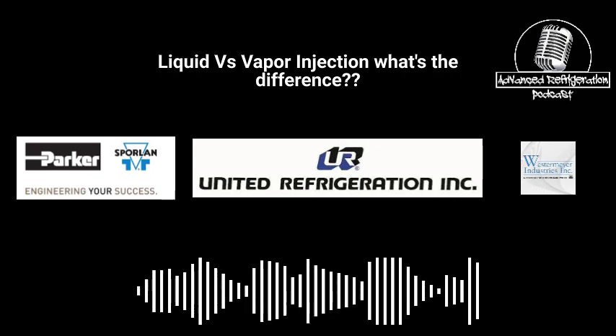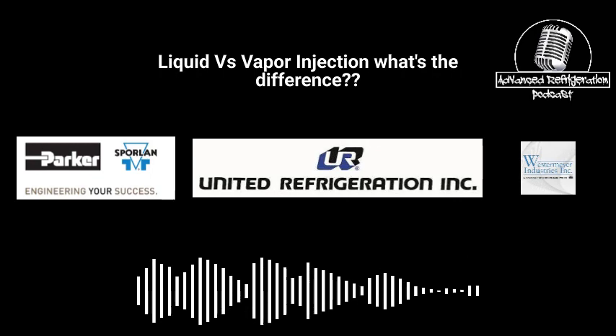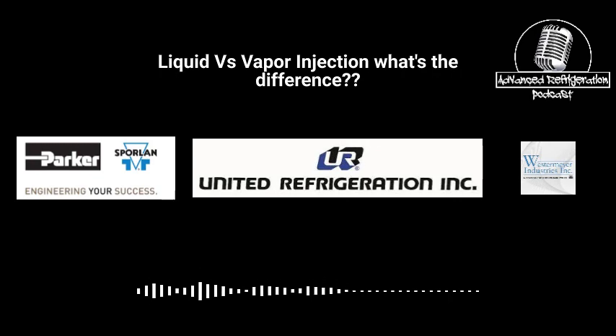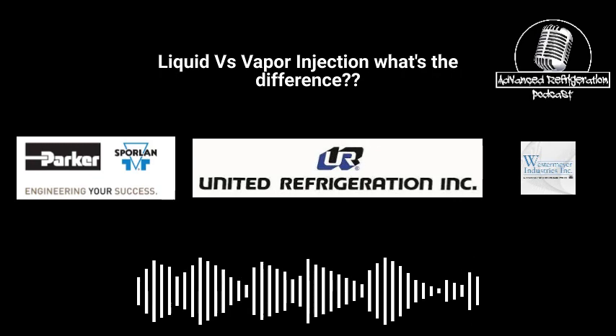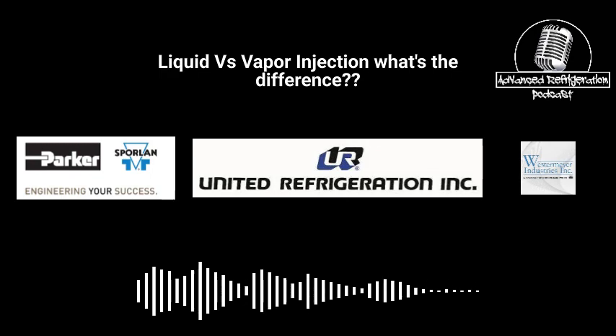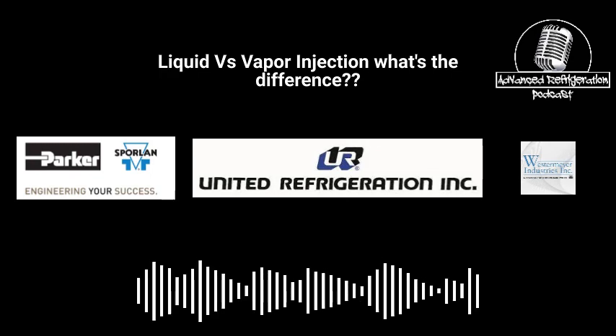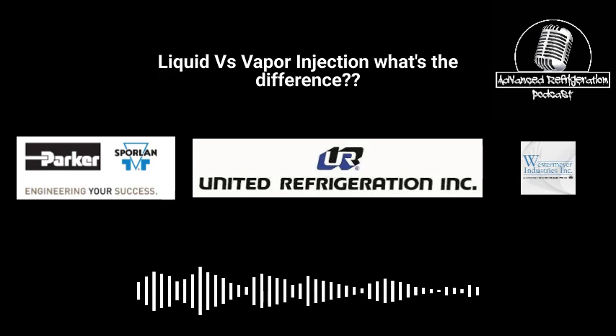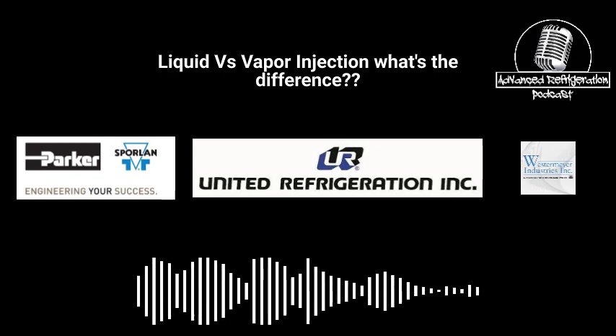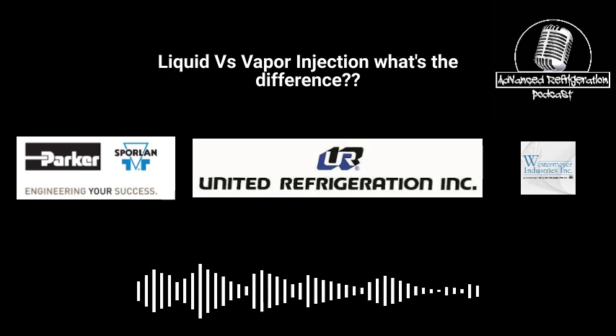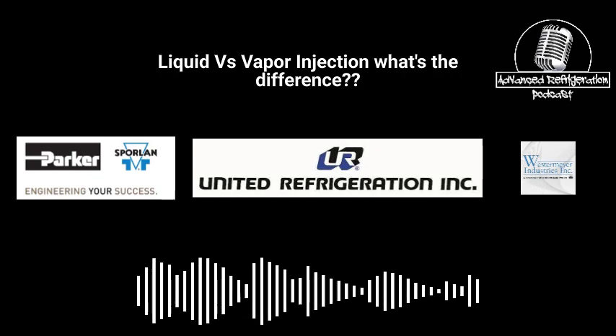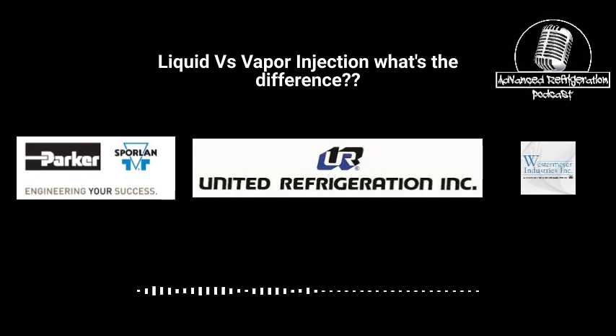Sure. So liquid injection is exactly what it sounds like. You're injecting liquid into the side of the compressor. Most compressor manufacturers will give you a diagram of the compressor and where to do the liquid injection. If you're dealing with a Copeland 6D, there's usually 2 places you have to inject. On a Copeland 4D, there's usually only 1 place. This is usually controlled by an electronic control, either your demand cooling module. Bitzer has their own form of demand cooling module that they use. Let's see what else.